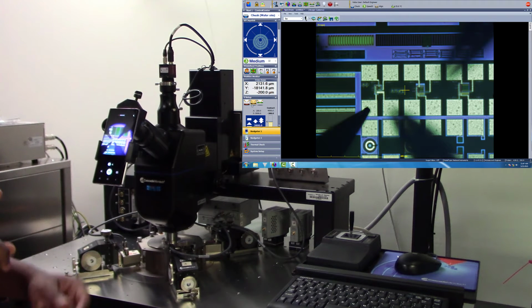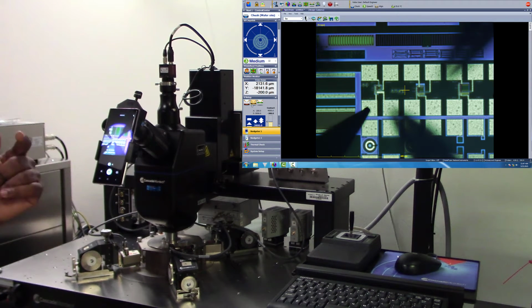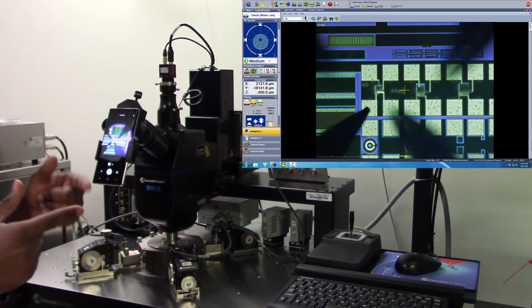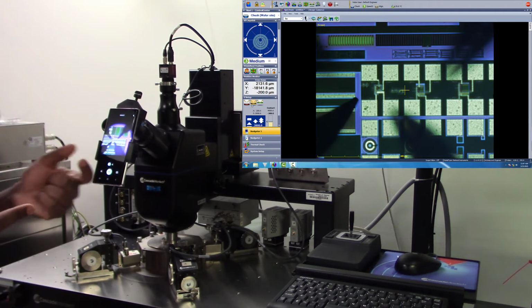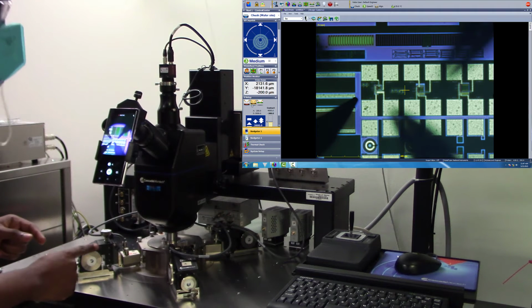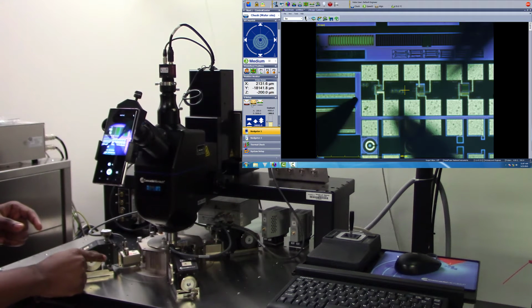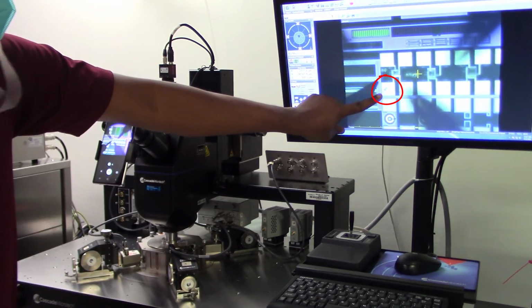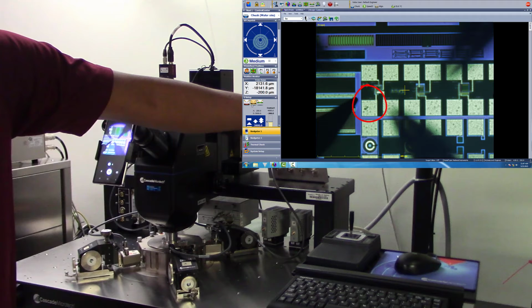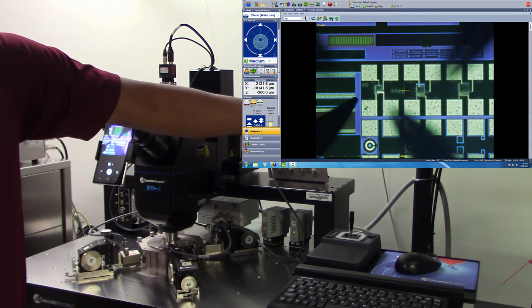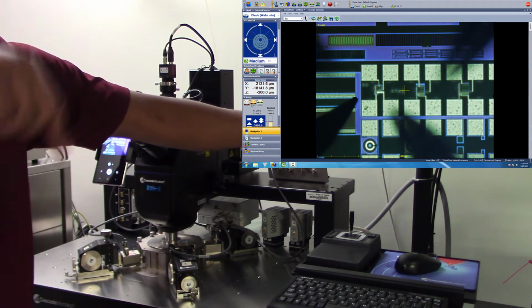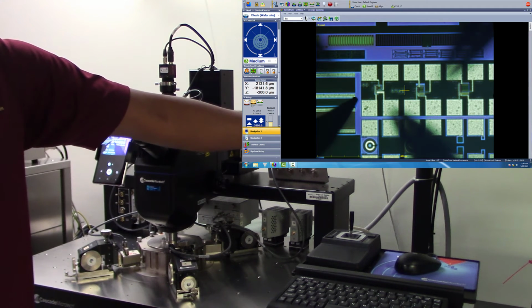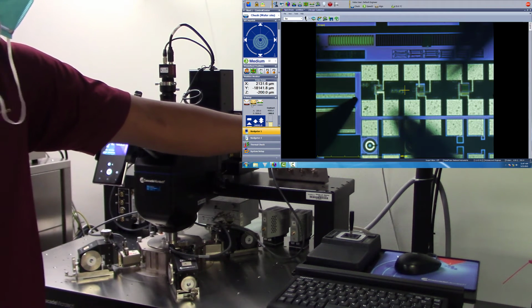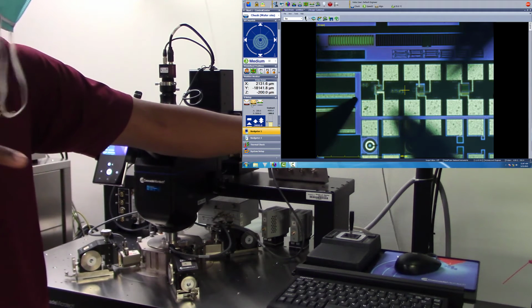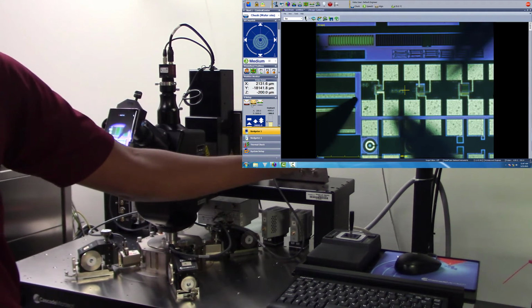Now, sometimes you might not see the scratch visibly with your eyes, especially when you have a tip that is not so good anymore. So to verify that, all you need to do is move your X position away from your device, and as you can see, you have a very small scratch on your device. That tells you that at that position, or at that Z height, you already have your probe tip coming in contact with your device whenever you go into your contact mode.